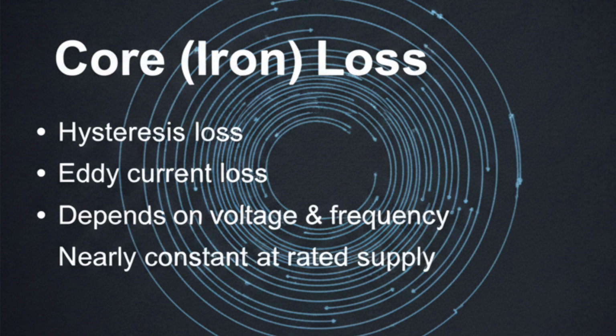Now let us discuss core or iron loss. This loss occurs in the laminated stator core due to alternating magnetic flux. It consists of 2 components, hysteresis loss and eddy current loss. Hysteresis loss depends on frequency and magnetic material, while eddy current loss depends on the square of flux density and frequency. Because supply voltage and frequency remain almost constant in normal operation, core loss is considered nearly constant from no load to full load conditions. This is why in testing we often measure it during no load test.